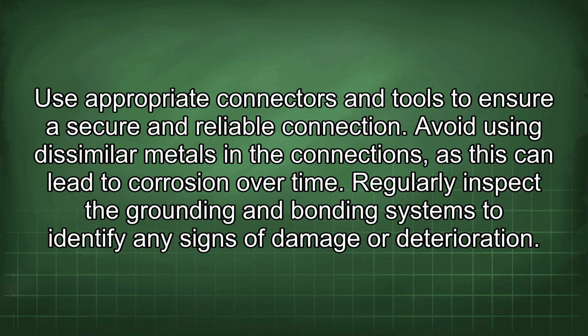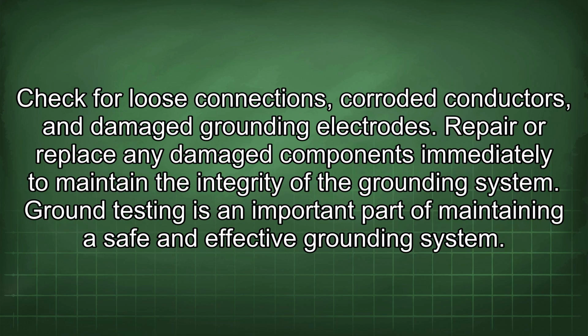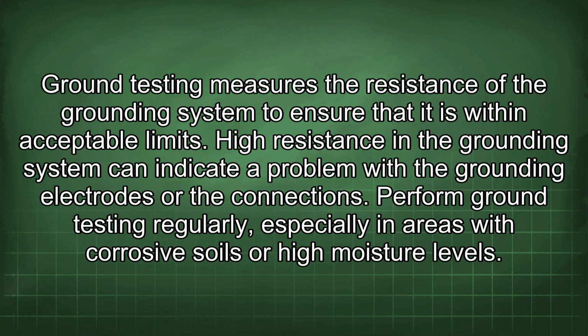Regularly inspect the grounding and bonding systems to identify any signs of damage or deterioration. Check for loose connections, corroded conductors, and damaged grounding electrodes. Repair or replace any damaged components immediately to maintain the integrity of the grounding system. Ground testing is an important part of maintaining a safe and effective grounding system. Ground testing measures the resistance of the grounding system to ensure that it is within acceptable limits. High resistance in the grounding system can indicate a problem with the grounding electrodes or the connections. Perform ground testing regularly, especially in areas with corrosive soils or high moisture levels.